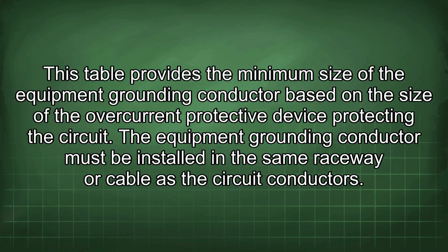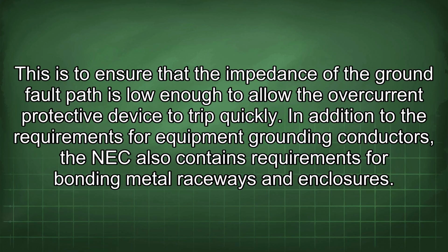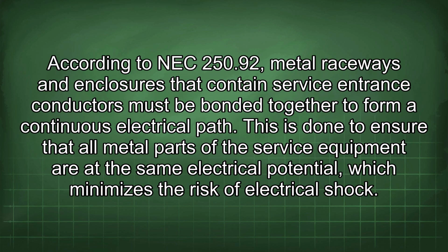The equipment grounding conductor must be installed in the same raceway or cable as the circuit conductors. This is to ensure that the impedance of the ground fault path is low enough to allow the overcurrent protective device to trip quickly. In addition to the requirements for equipment grounding conductors, the NEC also contains requirements for bonding metal raceways and enclosures. According to NEC 250.92, metal raceways and enclosures that contain service entrance conductors must be bonded together to form a continuous electrical path. This is done to ensure that all metal parts of the service equipment are at the same electrical potential, which minimizes the risk of electrical shock.